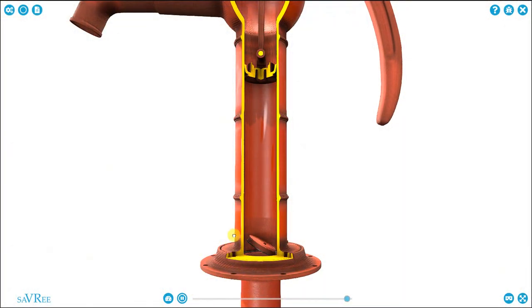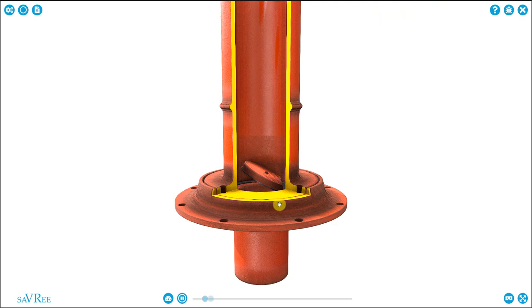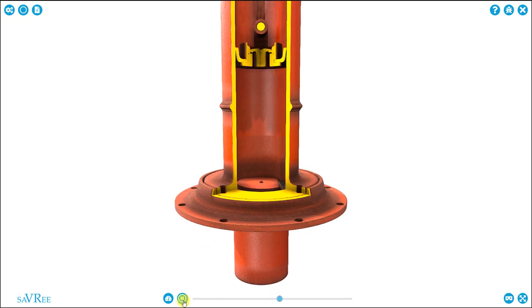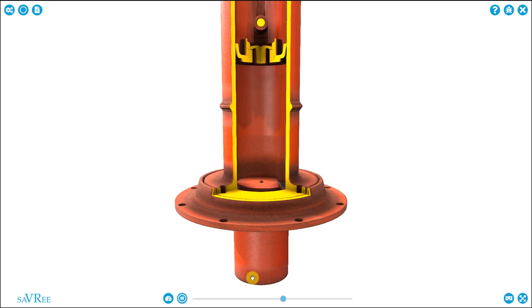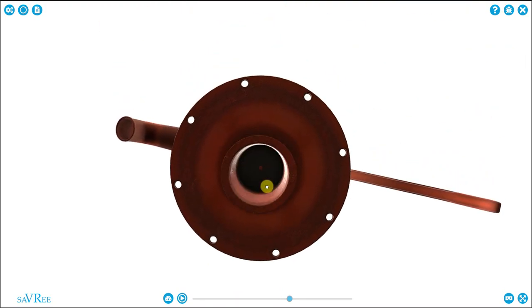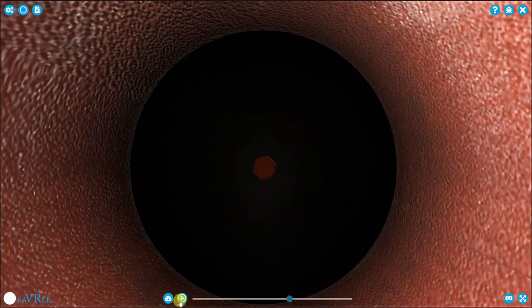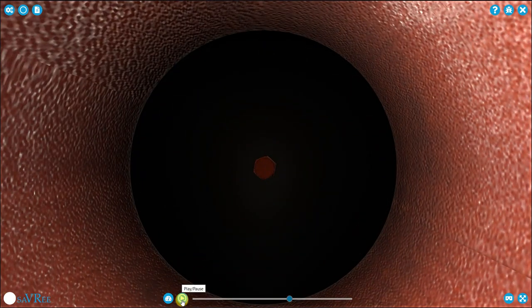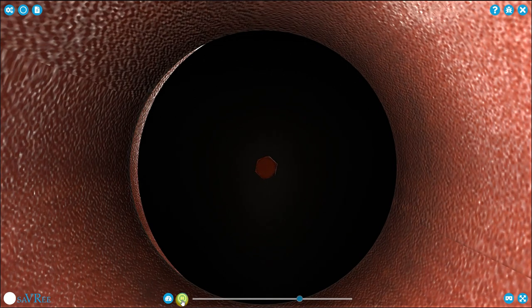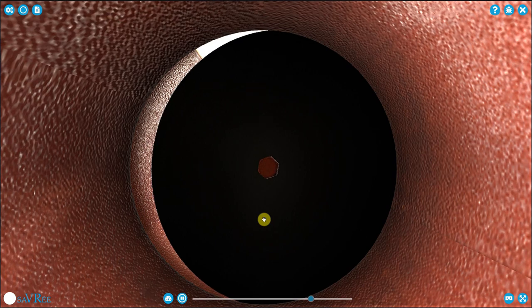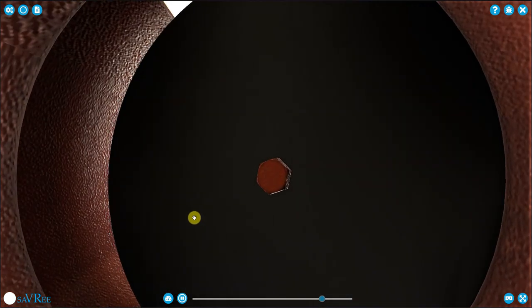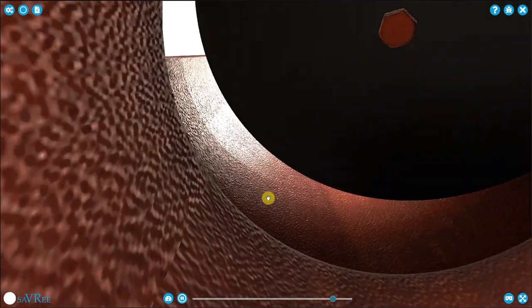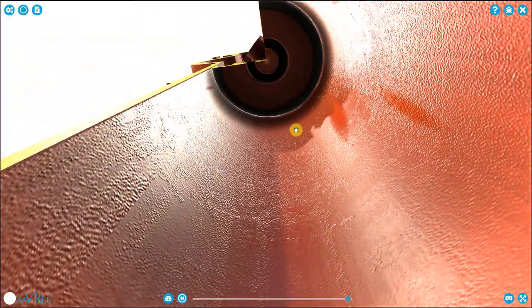So let's run through it again. We want to draw fluid into the pump. I'll find the right position for that. That's going to occur as the piston reaches the lowest point of its transit. So now we're creating a negative pressure in this space here on the underside of the piston and the top of the foot valve. That's going to cause fluid to be drawn in through the suction pipe. So in through here. And as the piston moves up, the foot valve will open. So the foot valve opens. The piston's still going upwards. If we were a bit of water or air, then we would be traveling through this space here.